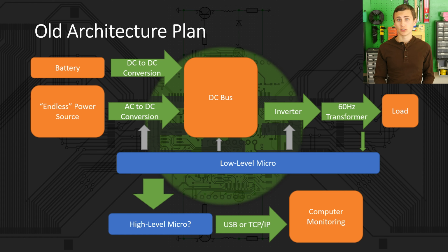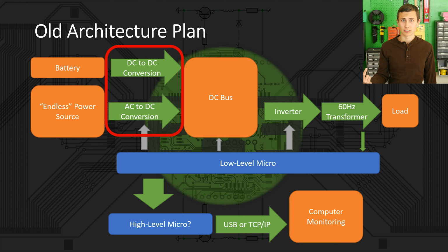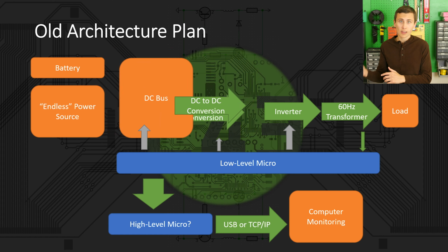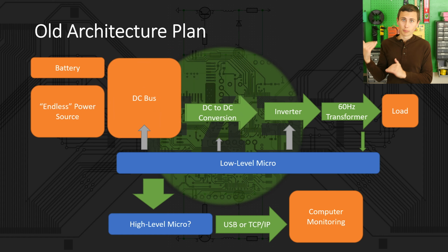The first issue is that we spec'd two redundant power supplies capable of handling the full output power of the system, which is a bit silly, to be honest, because we never need both supplies to be active. So we can just use one, eliminate a transformer, some high power switches, and a switch mode power supply by switching between the two DC sources before conversion to the DC bus, and then using the holdup of the bulk on that bus to keep the inverter running while we switch.